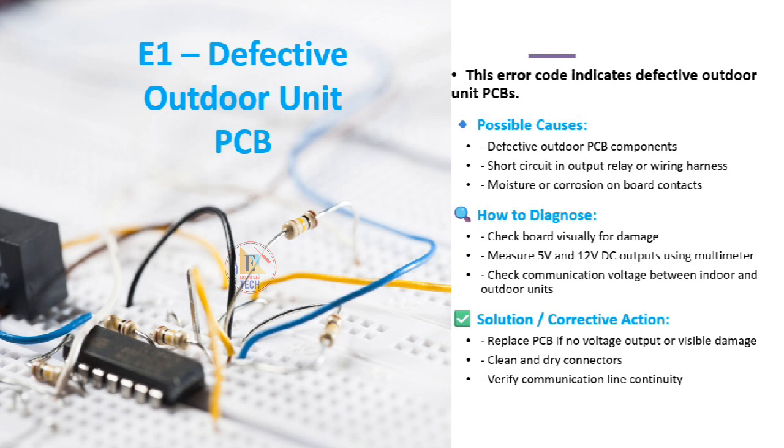Diagnosis involves visually checking the PCB, measuring 5-volt and 12-volt DC outputs with a multimeter, and checking communication voltage between indoor and outdoor units. If no voltage output or visible damage is found, the PCB should be replaced. Connectors should be cleaned and dried, and communication line continuity must be verified.